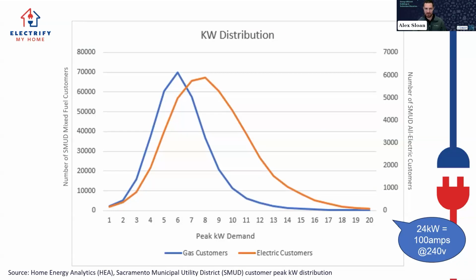Breaking it down further, this chart is from SMUD customers in Sacramento. On the bottom is peak kilowatt demand - the max power used at any 15-minute interval across a year - and the number of customers, either mixed fuel with gas in the home, or all-electric homes in orange. The main takeaway: a 100 amp panel, considered small in many cases, actually has 24 kW, which is off the charts here. So when you look at actual consumed power and energy data for an electrical panel, we're not using anywhere close to its max availability.